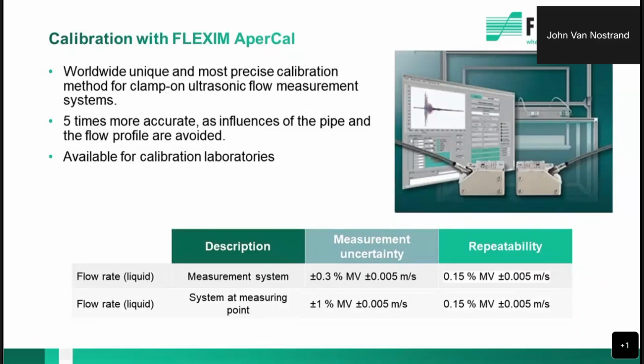And as I mentioned, the conventional calibration is a comparison of a device under test with a reference instrument in the wet flow. However, with flow profile becoming very important, what we're doing here is we're actually putting the transducers in a wet bath and moving them very precisely. Essentially, we simulate the flow velocity by moving them very slightly. And this is done with a laser alignment tool. And it's very accurate, and it's accepted as a calibration methodology in many industries, including the water industry.